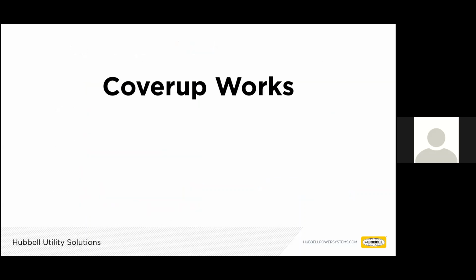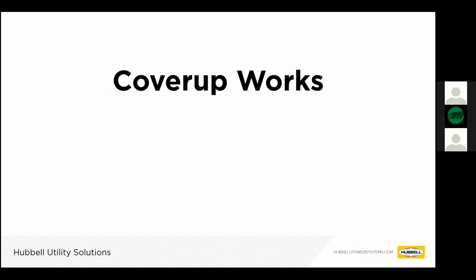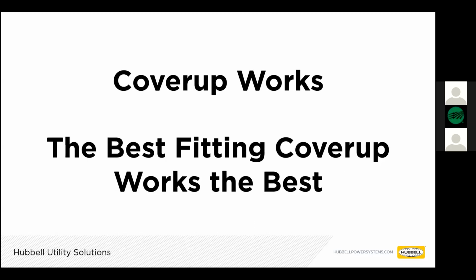So with that, I will end. I think we're hopefully about right on time here to leave some time for questions, but I want to leave the takeaway with you that cover up definitely works. You definitely can use wildlife mitigation guards, cover up, to really drive outages towards zero. There are several case studies that we can provide that demonstrate that wildlife mitigation guards, particularly Green Jacket in substations, can be very close to 100% effective. So cover up works, but absolutely the best fitting cover up works the best.